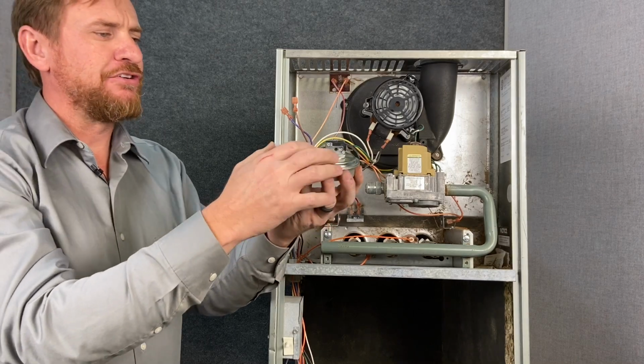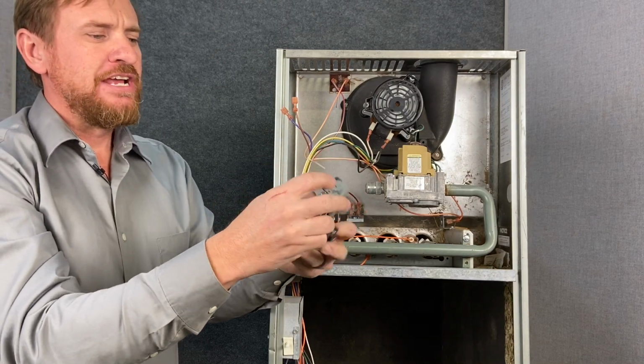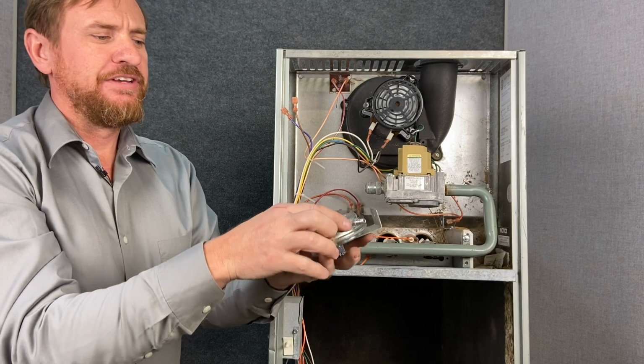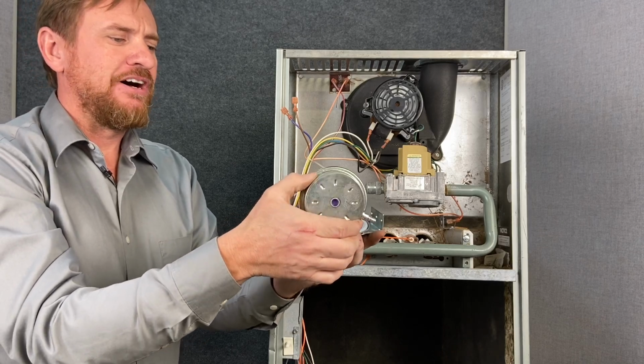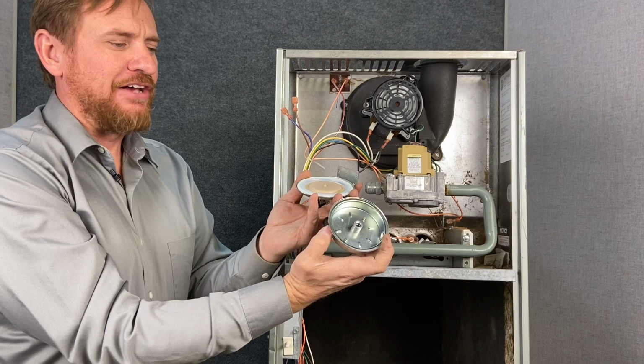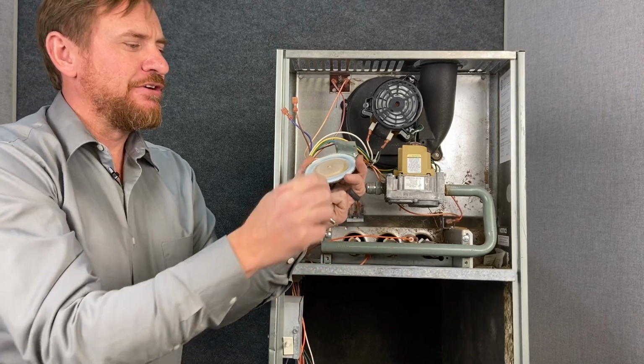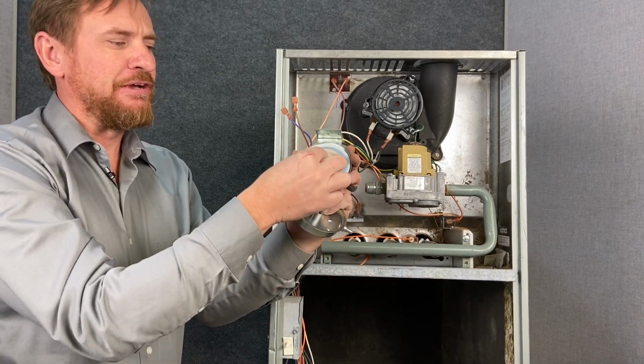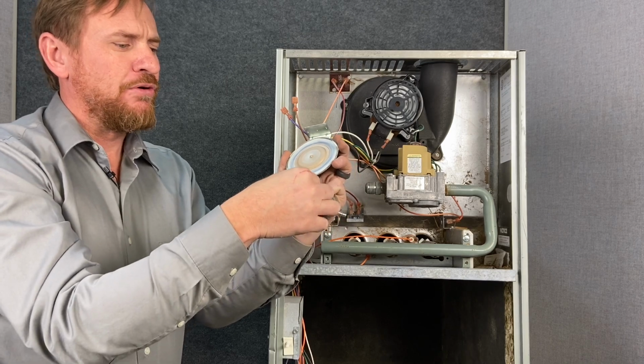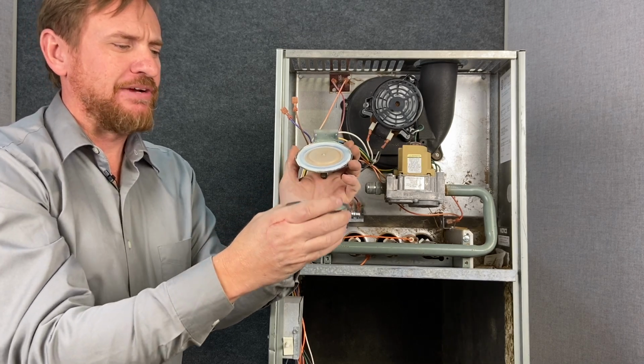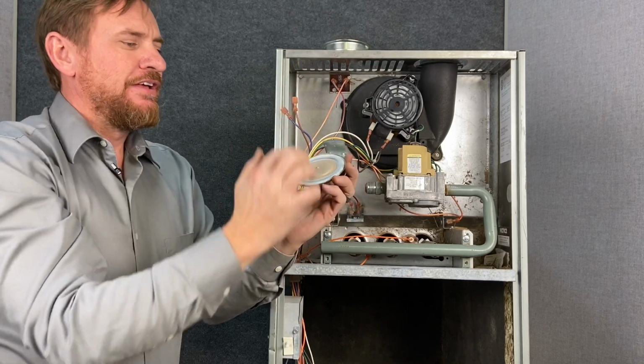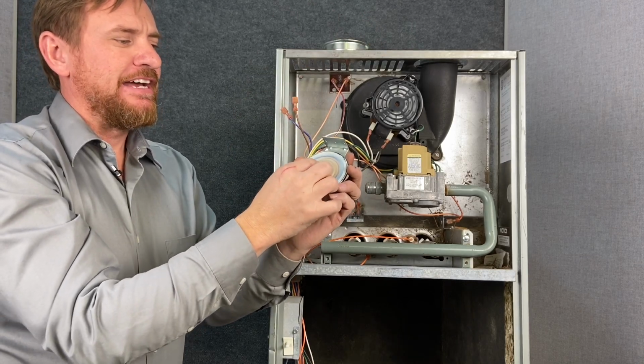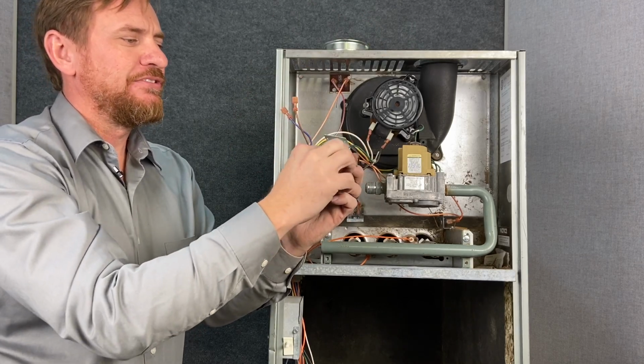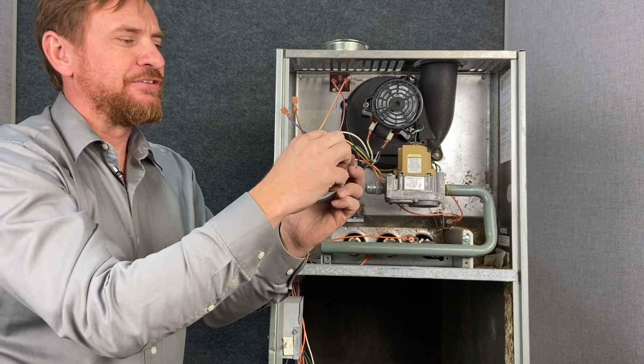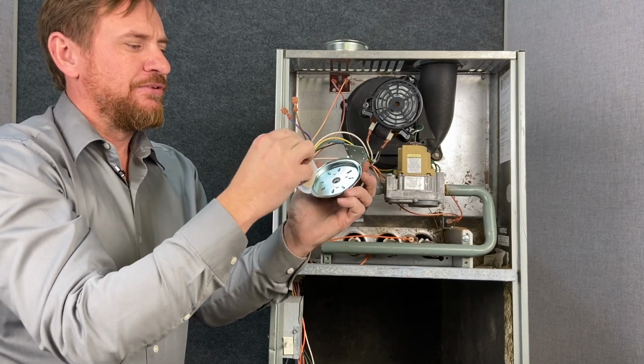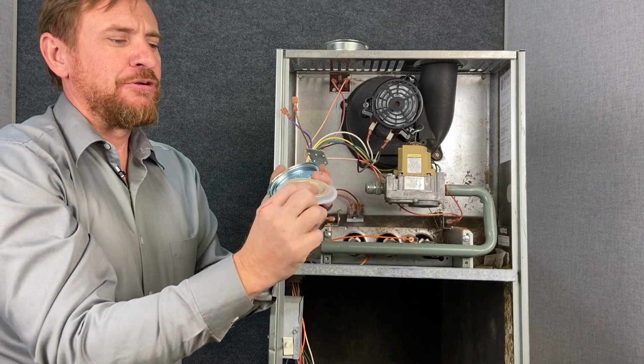So here we have our pressure switch, and this is just a micro switch, and then we have the connector for a hose here. So once we take this piece off, it's just a hollow housing, and if we notice, there's also a little spring right here. The spring would be in the center of this diaphragm and held right in the center of that piece right there. So with that removed, it pulls a vacuum, it moves this diaphragm here. So we're going to take this loose, just going to pull it loose. Notice there's a nice little seal on it. That's what holds that vacuum. And there's this little button on the end.